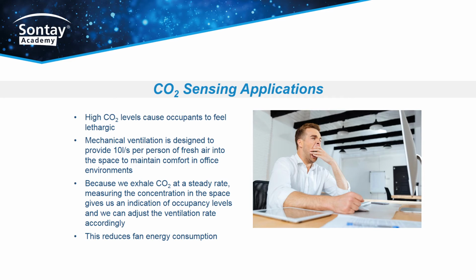Subject to a minimum fresh air rate, when CO2 concentrations start to fall, we can slow the fresh air fans down to deliver less air and benefit from the energy savings afforded by a VSD when running a motor at a reduced speed. Comfortable conditions are usually around 1000 to 1500 ppm, but different scenarios require different ventilation rates. Lower CO2 levels aid people's ability to concentrate, and many educational specifications now require a level of 750 parts per million.